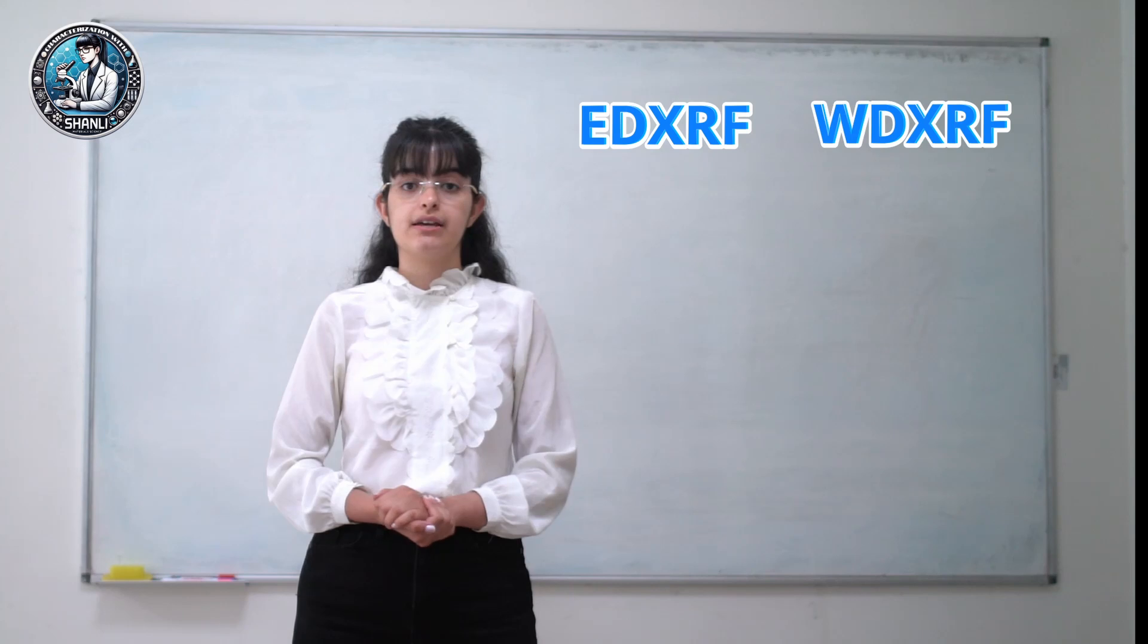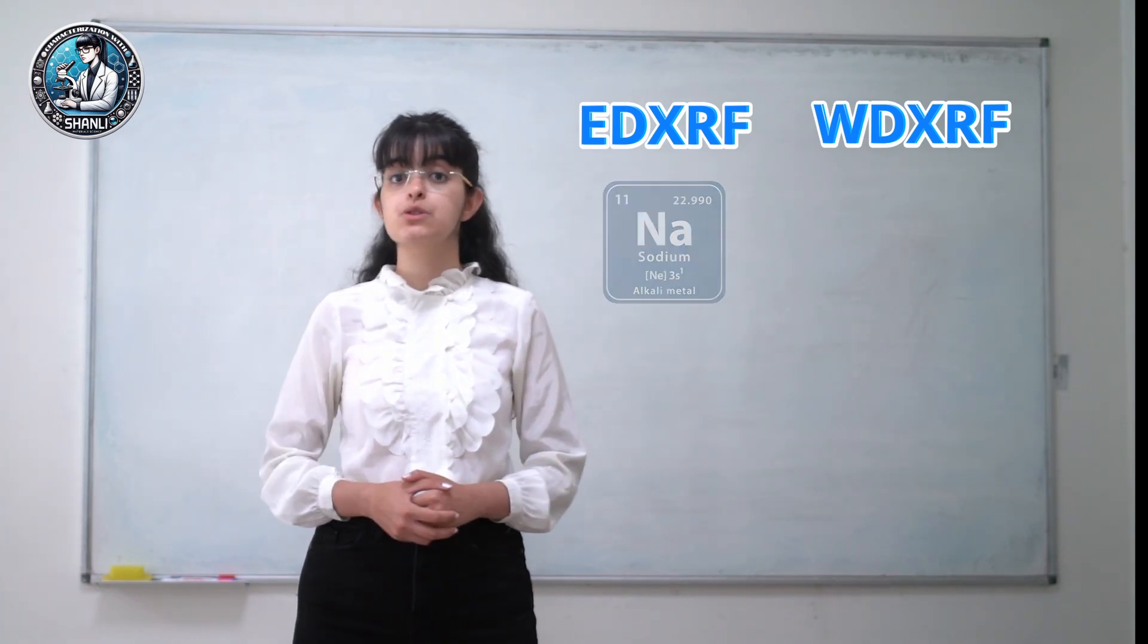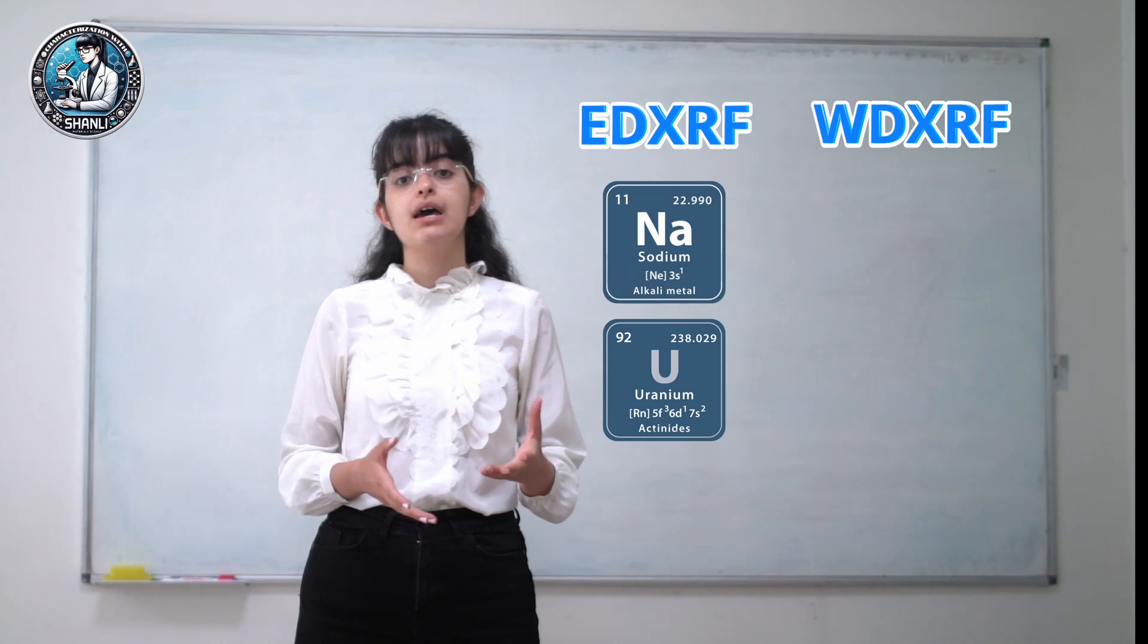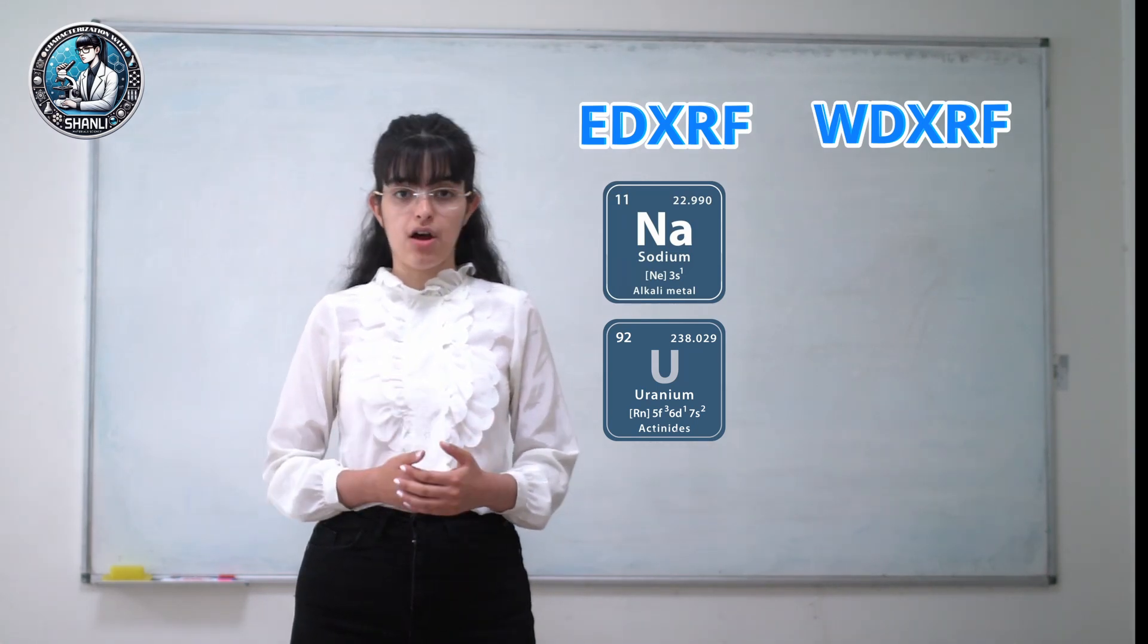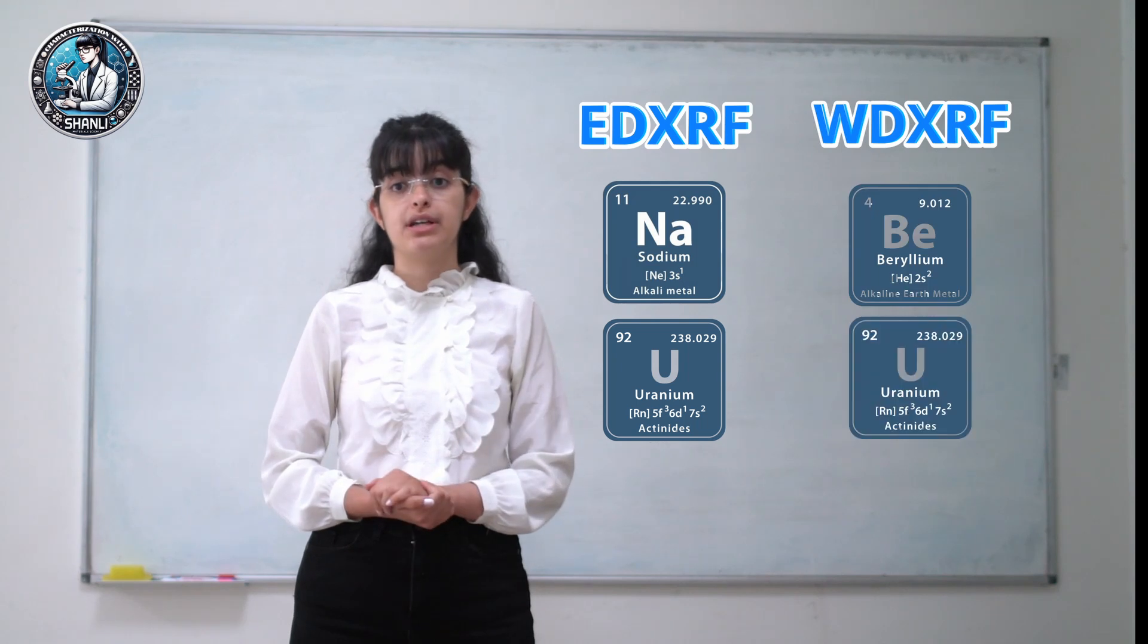For example, EDXRF typically enables the detection of elements ranging from sodium to uranium. However, the WDXRF offers an even broader range of elements from beryllium to uranium.